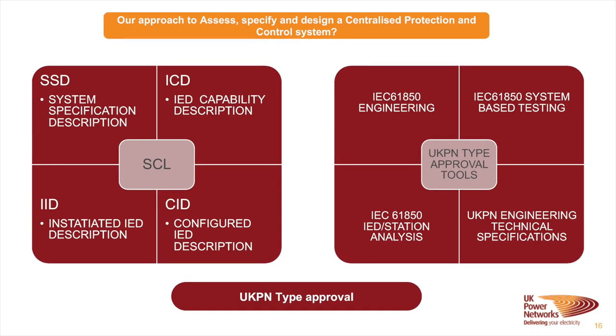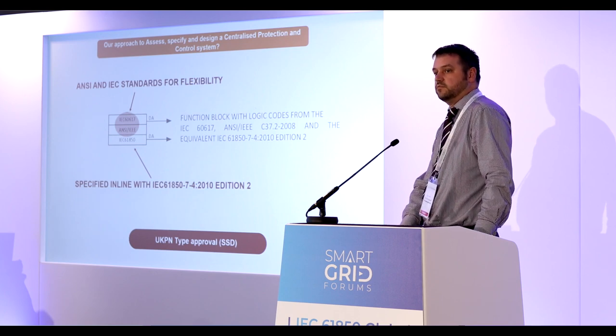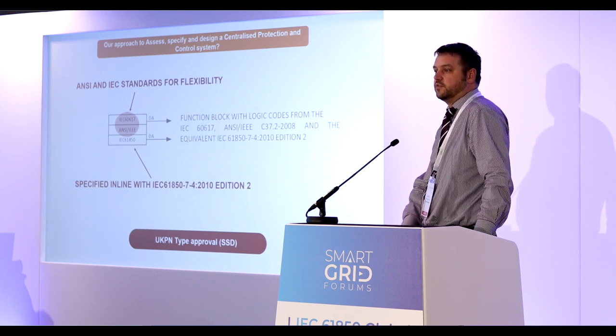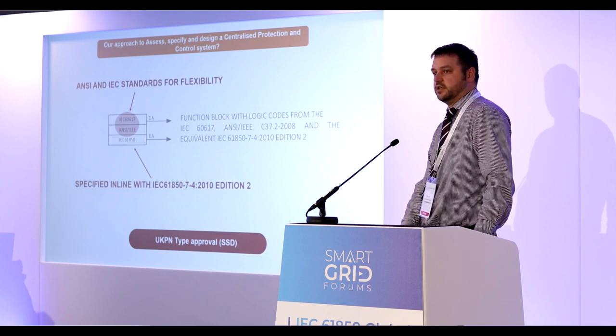Once hardware and functions are assessed within the centralized device, we move into the SSD specification for the UKPN type approval, using SCL files and IEC 61850 system-based testing. As background: we don't currently use 61850 at all — we've got two substations that were pilots quite a few years ago at the station bus level, but it never really took off, which was disappointing when I started this rolling asset management program two years ago.